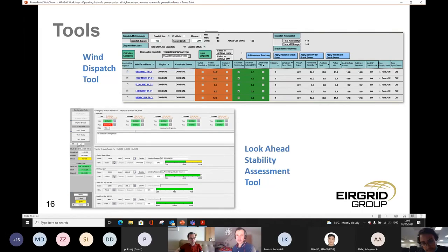From the real time system, we get a state estimation of the real time condition of the power system, a full network model, full state estimation, with a real time element. It's doing a full quasi-dynamic voltage stability assessment, but also a full transient stability assessment. We have all the dynamic models of the generators, loads, interconnectors, and all devices connected to the system.